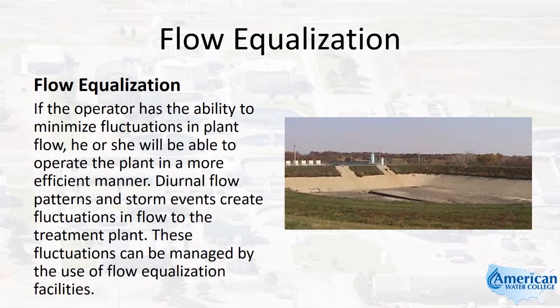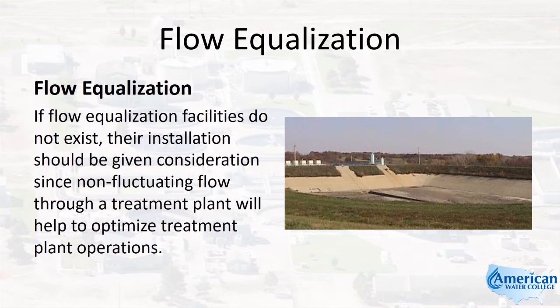If the operator has the ability to minimize fluctuations in plant flow, he or she will be able to operate the plant in a more efficient manner. Diurnal flow patterns and storm events create fluctuations in flow to the treatment plant. These fluctuations can be managed by the use of flow equalization facilities. If flow equalization facilities do not exist, their installation should be given consideration since non-fluctuating flow through a treatment plant will help to optimize treatment plant operations.